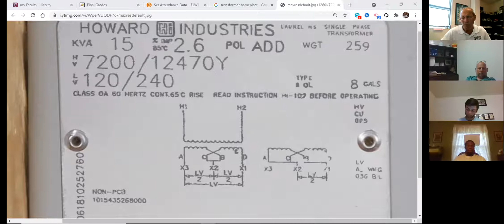Now, if we put 30 lights out there, 1,000 watts each, and we've got a 15 kVA transformer, pretty much the transformer is going to overheat and die, or a fuse is going to blow on the transformer, melt out. It just won't be able to power those lights. Gotcha, okay, so for this purpose we're just going to use this 15 kVA.